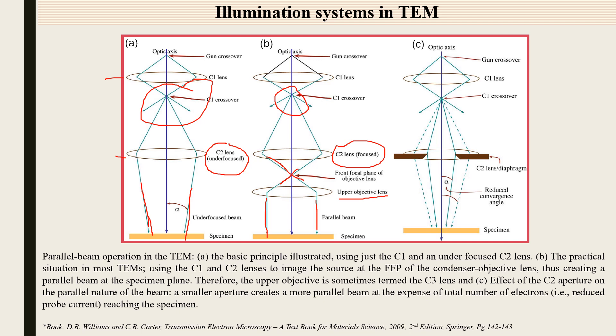In another example, if you insert a small aperture around C2 — acting like a diaphragm — the diverged beams are blocked and only the remaining beam reaches the sample. The small aperture creates a more parallel beam, but at the expense of the total number of electrons: the probe current reaching the specimen is reduced compared to the second example where a parallel beam with more electrons is used.